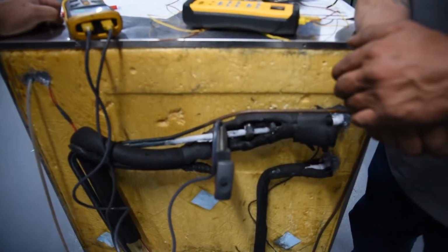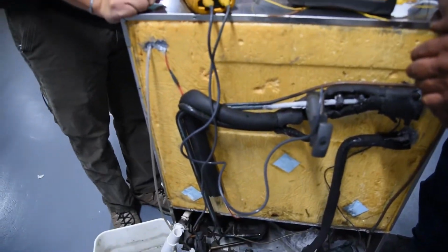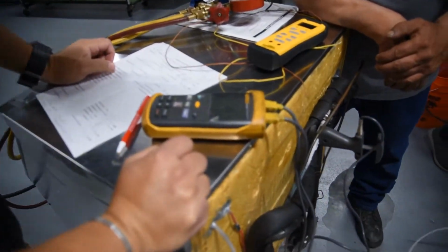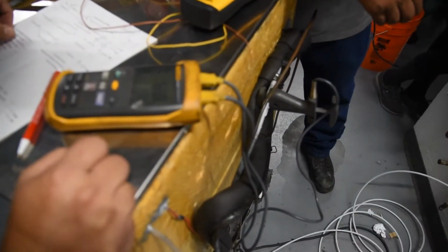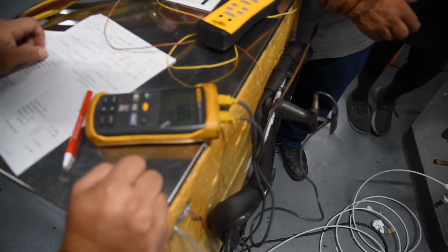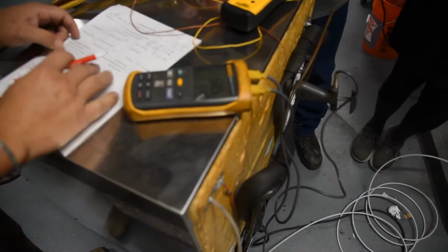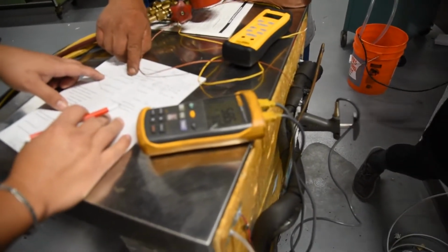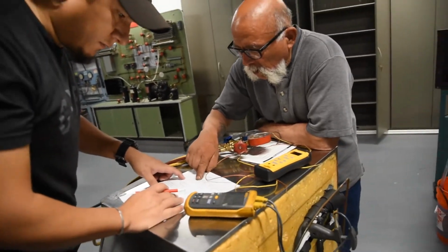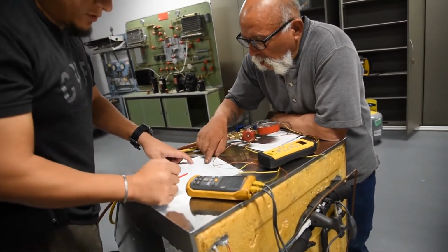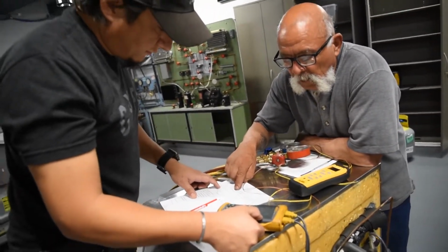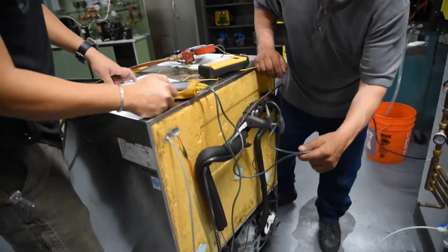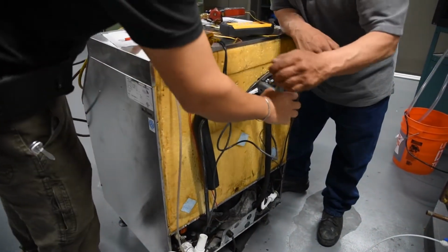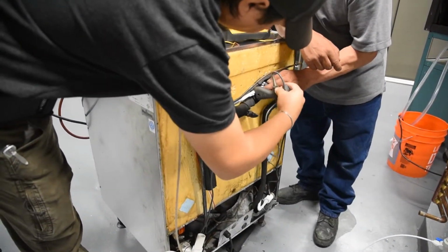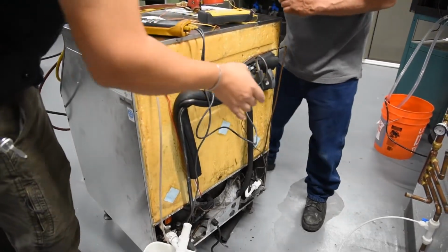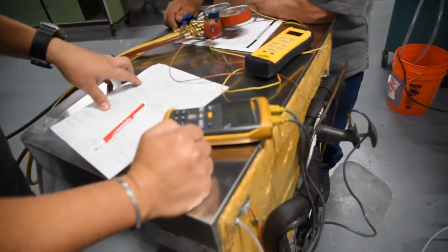Yep. And what are we getting now? Okay. It's dropping. We'll call it 58. So we'll change this. 58, we had 50 before. I think these are... oh, that's right. Maybe because of the cycle, but it should be dropping more, maybe. Yeah, because it can't be 58 degrees. Why? Because it has ice. It's got to be 32 degrees at least. There you go. Well, we weren't making good contact.